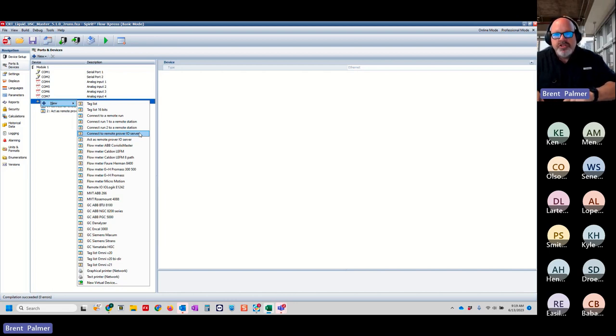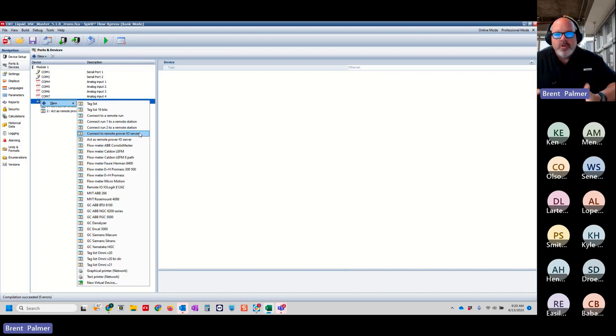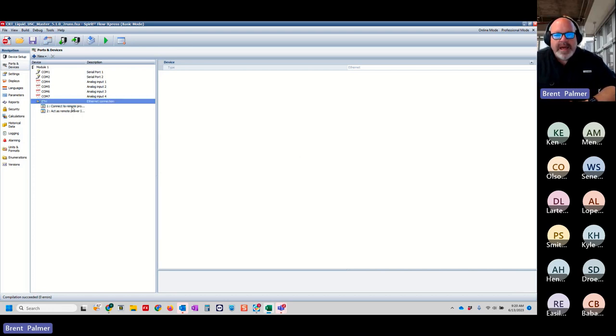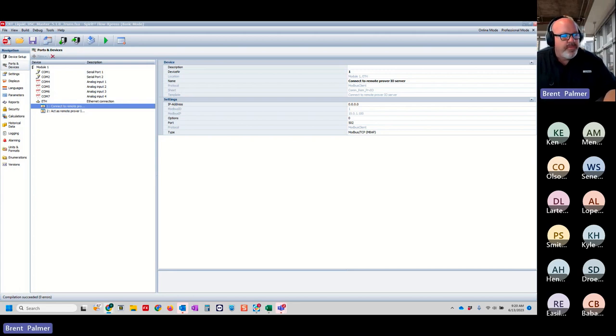When sharing a prover, the module serves up the temperature, pressure, and density from the prover and tells the prover to launch; detector switches are still jumpered to each module that has a meter. A remote module can have the prover connected with the launch command there, and all remote modules connect to the prover module and tell it to launch while receiving temperature, pressure, and density — but doing their own proving calculations on the module that has the physical meter. Depending on whether you're a server or a client, you put in the right communication template, load the application into the flow computer, and begin setting up your settings.